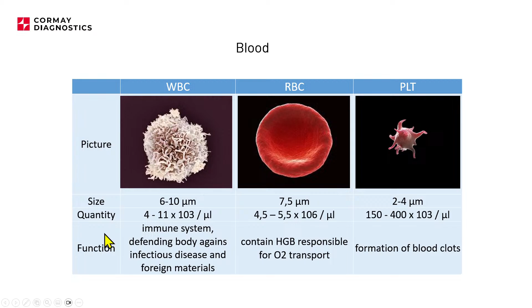And PLT number, as you can see, the size of those is smaller than size of the white blood cells. So actually, the number of PLTs is also significant, but since the size of those is smaller than size of the white blood cells, device can ignore PLTs, which will be still present in the WBC chamber. It will not take them into consideration during the white blood cells measurement. RBC and PLT, they are only measured in the RBC PLT chamber. WBCs are measured in the WBC chamber.